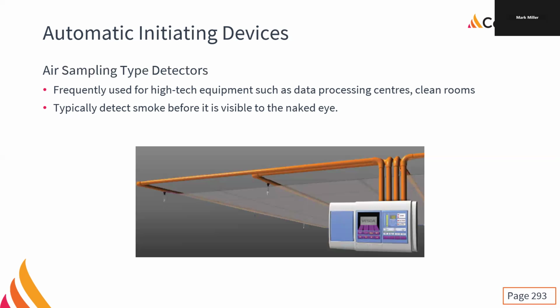As many VESDAs as I've installed for elevator shafts, I have gone in and removed the same number from those and other elevator shafts. Right? I am almost at zero for installed minus removed. I've probably installed 30 VESDA systems at this point, and I think I've removed like 28 somewhere around there. It's because of too many troubles with them. Right? Now, I think a lot of that is they're not properly configured.